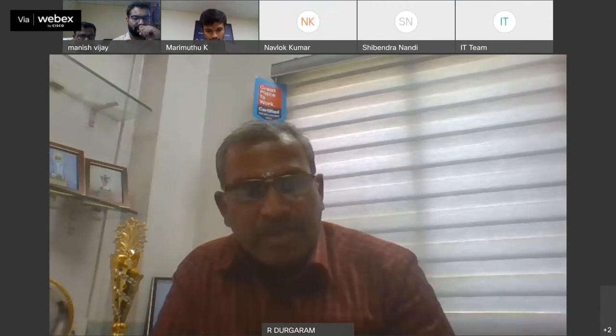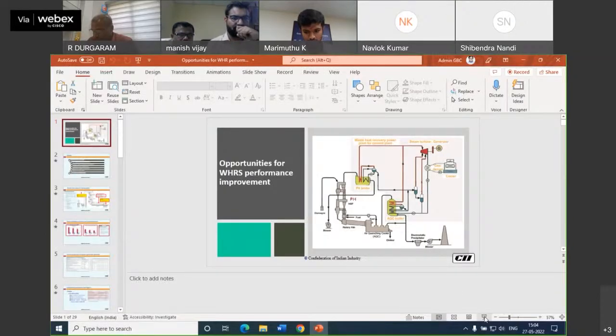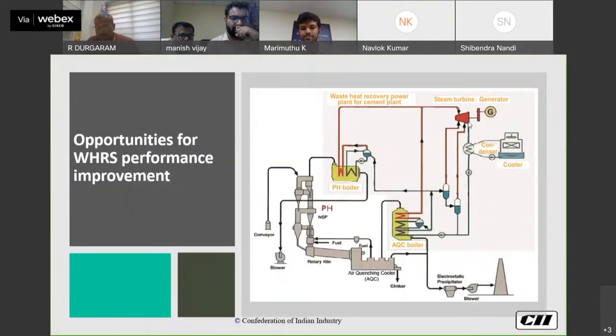That schematic diagram is very nicely prepared. About the air-cooled condenser, the saving of 2 lakh liters per day of water is a good initiation done by you people. And the case study about the malfunctioning of the dampers due to high DP across the WHRS and the false air ingression, all those things are nicely captured in our PPT. And one more attractive piece of information you have given, that you have switched over from multi-louver damper to guillotine damper. That is very good information for all of us.